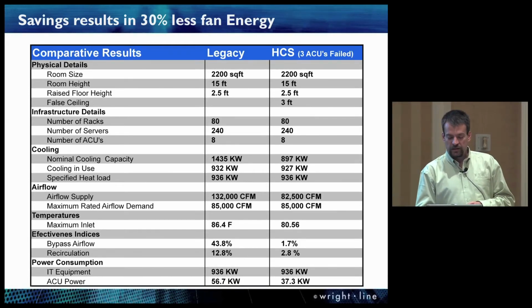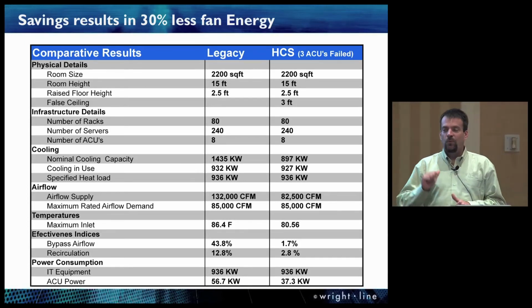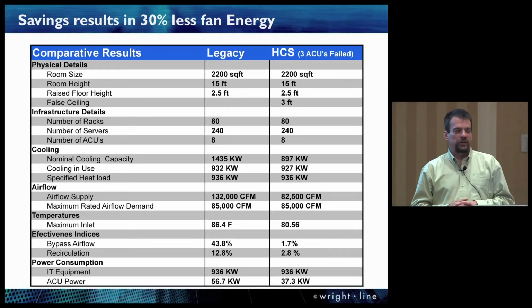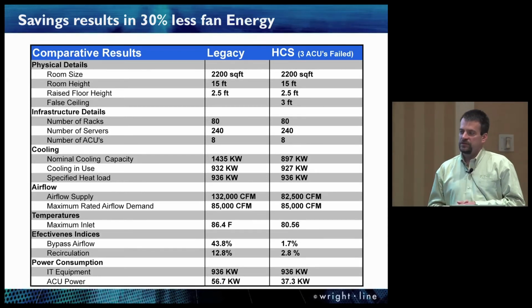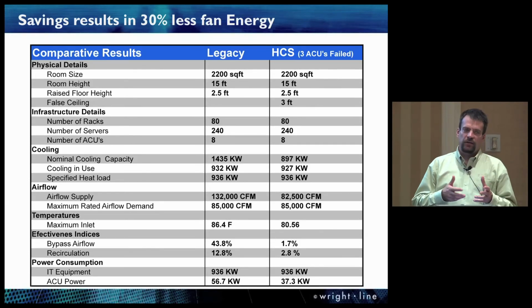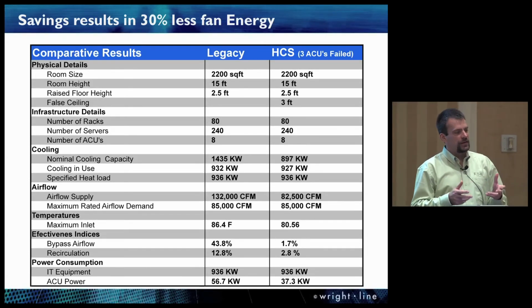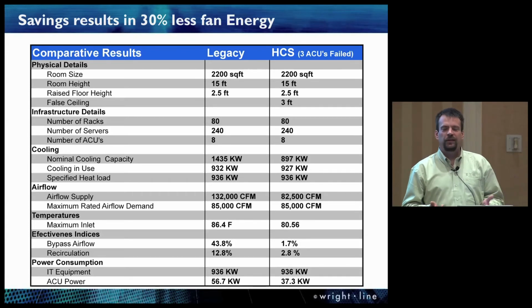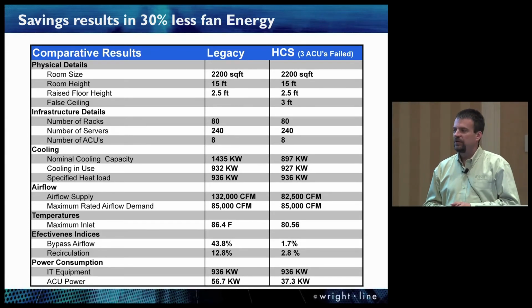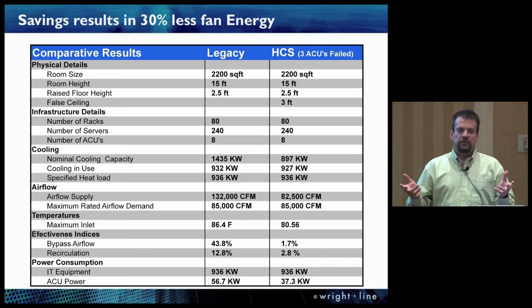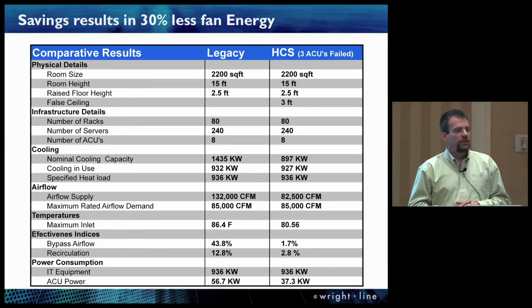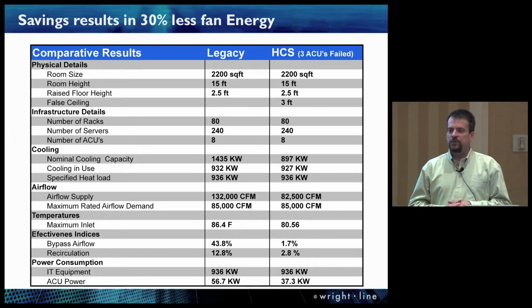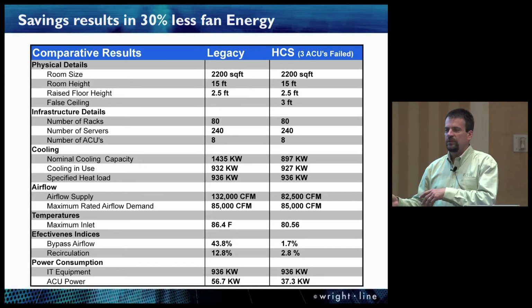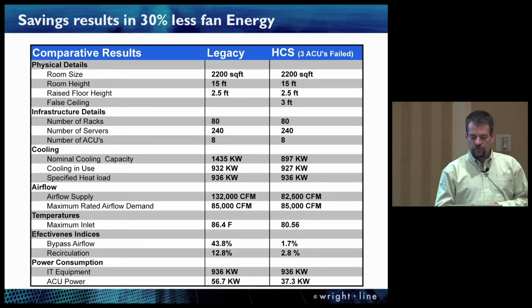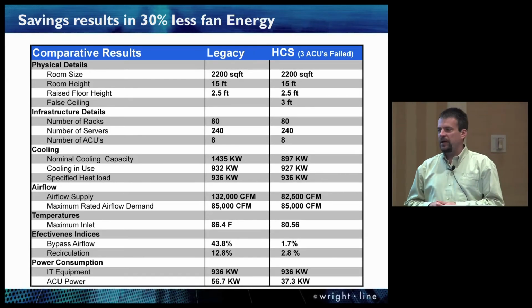You can see the maximum inlet temperature is actually one rack reporting over ASHRAE at 86 degrees Fahrenheit, but you're giving it 132,000 CFM. That's not necessarily matching supply and demand, but in a legacy system that is acceptable. And having 1 or 2 rack spaces that have some high temperatures that are either going to be abandoned as rack space or a hot spot that will not be populated is acceptable in a legacy design. Take that over to the heat containment design, and you're down below ASHRAE at 80.